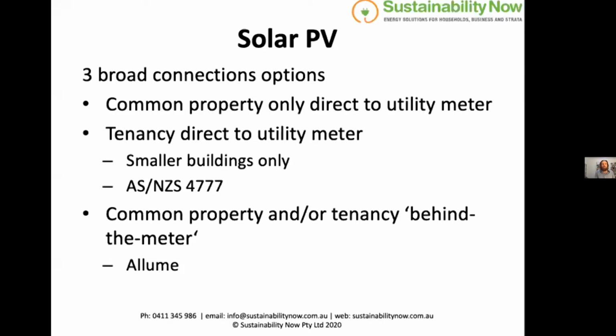There are 3 broad options to connect your solar PV system on your residential strata building. One is just on the common property, direct to the existing utility meter. You can also, if your building is configured the right way, connect a PV system directly to the tenancy meters - but that's really only suitable for smaller buildings. Otherwise the wiring starts getting complicated, wiring back to more than say 10 apartments, but it's not impossible.